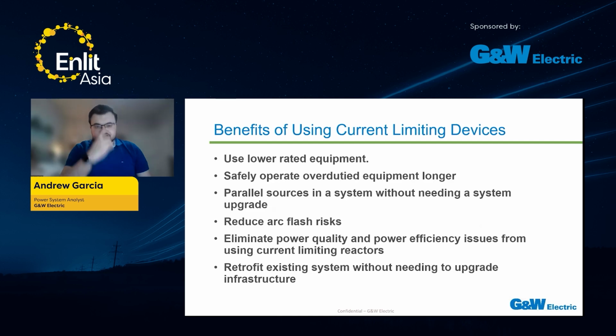So some of the benefits of using these devices are as follows. You can use lower rated equipment. So let's say there's 60 kA of fault current available, but you only have 40 kA equipment available. Using a current limiting device could bring the fault current down to a manageable level, so you can use the lower rated equipment and save quite a bit of money or keep your project on time. You can safely operate over-duty equipment longer. Say you have an older facility that has a lot of over-duty equipment. A current limiting device can provide sufficient protection such that now all of your nearby personnel and equipment are completely safe, at least within the confines of just having proper electrical protection.